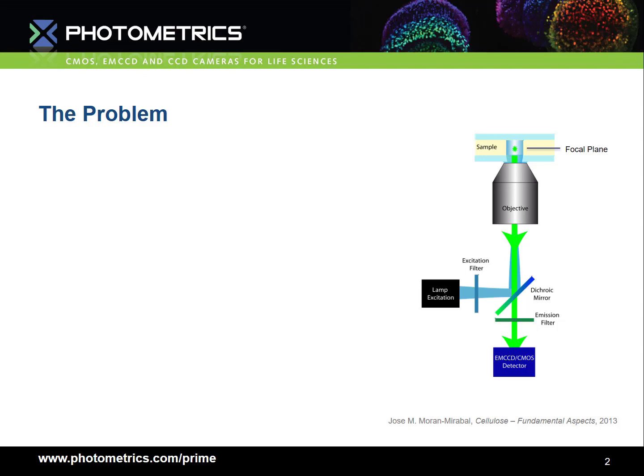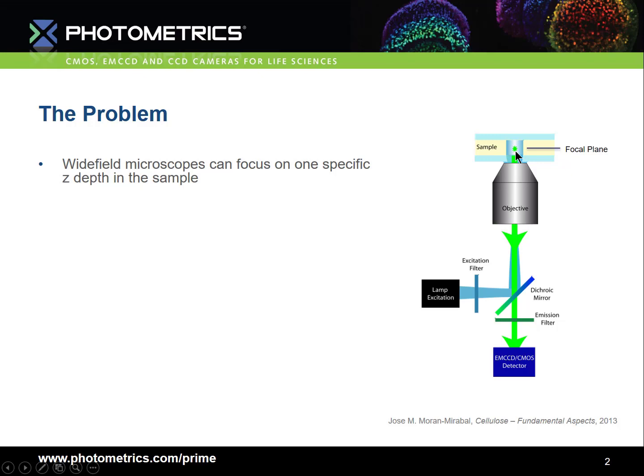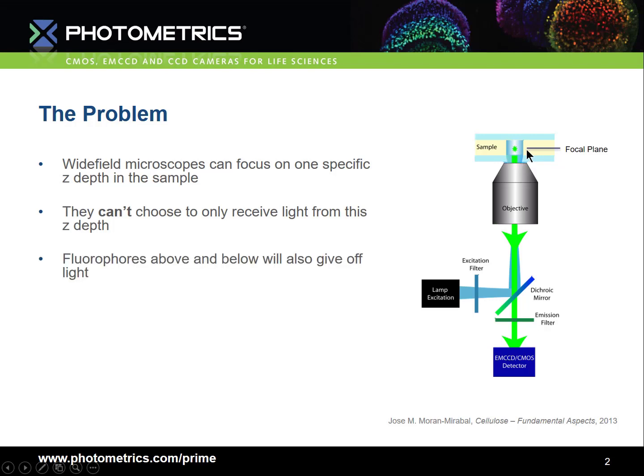To begin with, we'll start by looking at the problem with conventional wide-field fluorescence microscopy. Here we have a schematic of a wide-field system, and here we have a sample. We can choose to focus on a certain focal plane within the sample for the features that we want to observe. But what we can't do with a wide-field microscope is choose to only receive light from this focal plane. Fluorophores from above and below our chosen focal plane will also be illuminated and also give off light, which will reach our detector.